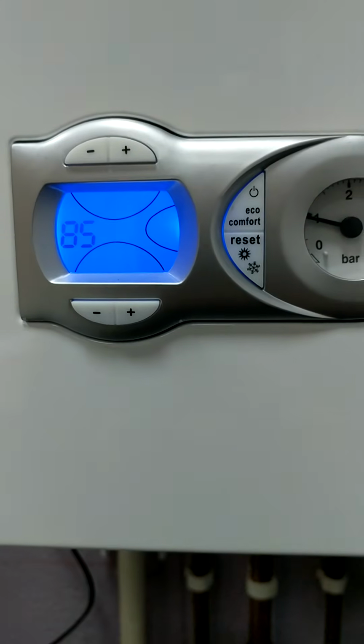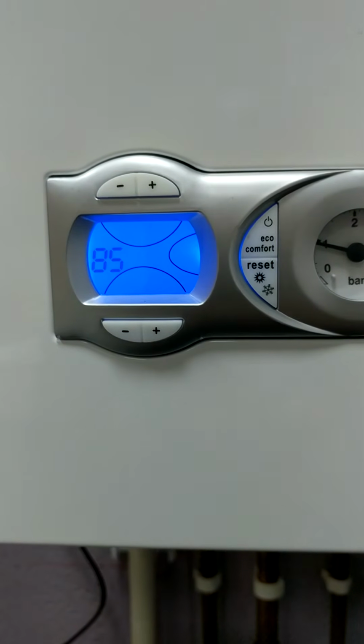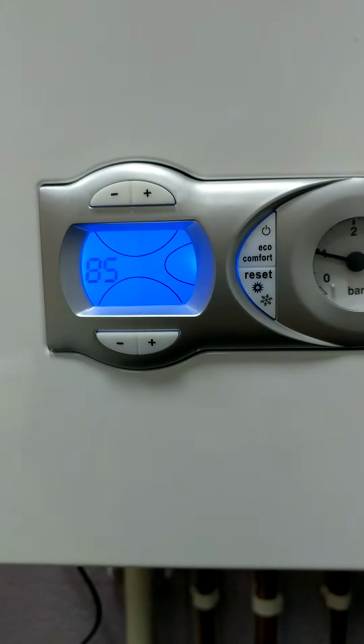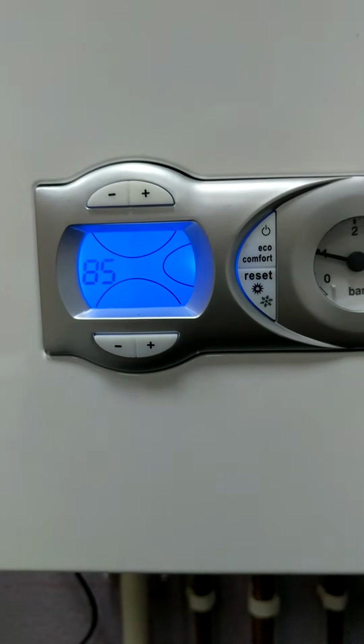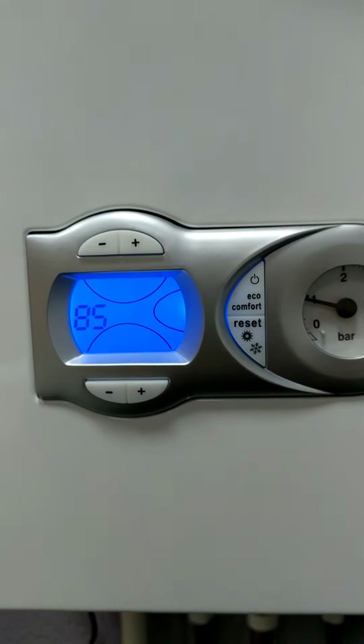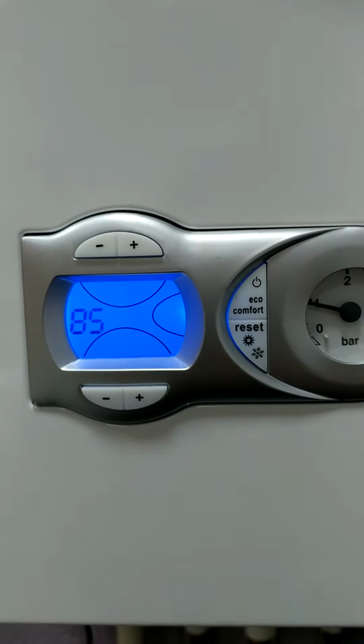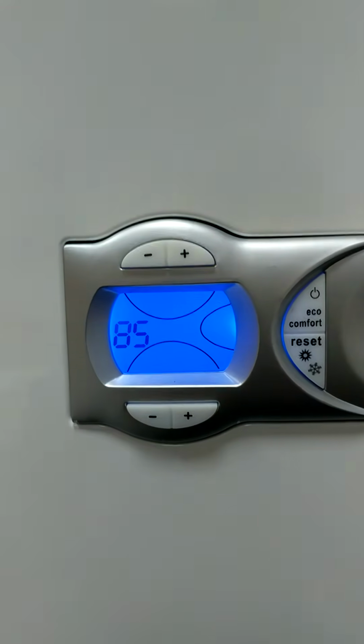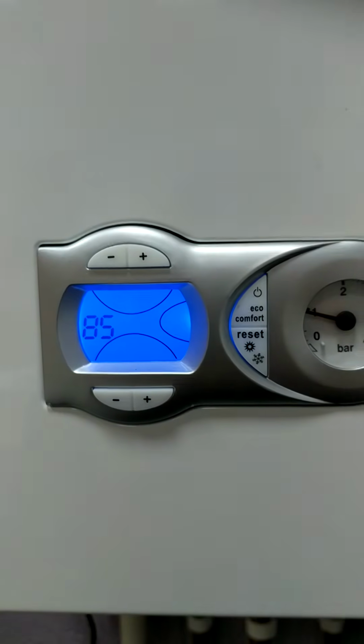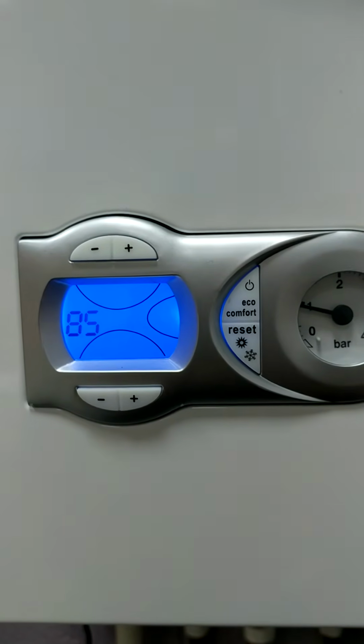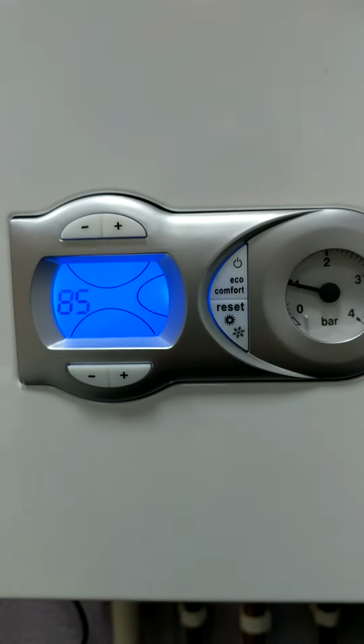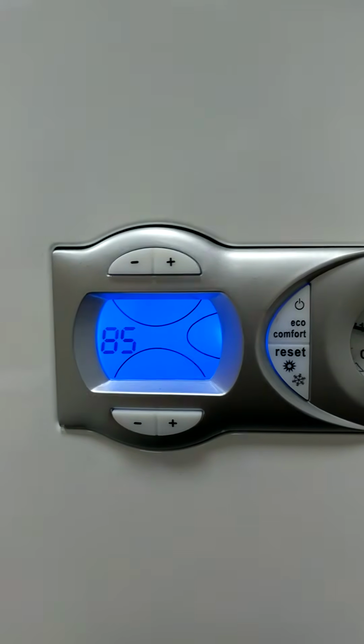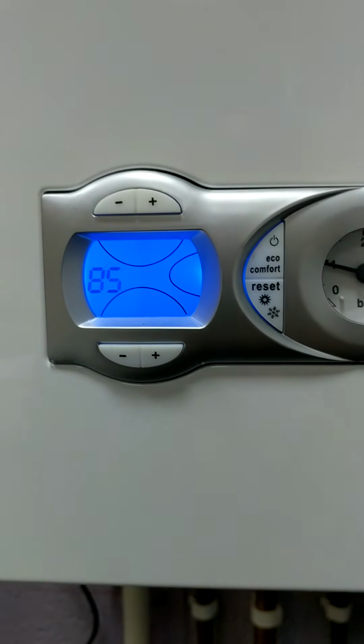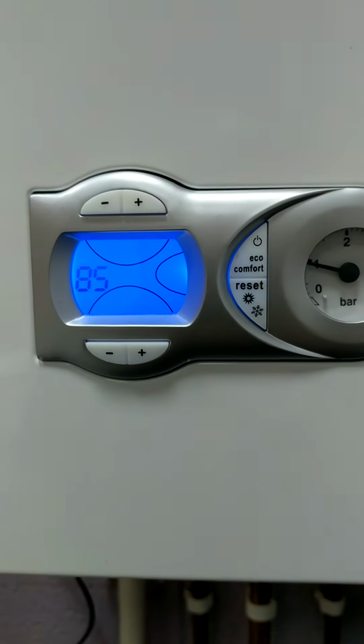What I will say, when you do commission the boiler, make sure you do your commissioning first, so you can get your kilowatts, you range rate it, and you get all the correct kilowattage and range rated temperatures and kilowatts that you use. Then after you've done that and you fill in the benchmark, then you can range rate it down. Because if it's a 25 kilowatt boiler and you set it up and you try and range rate it, you might end up coming into about a 12 kilowatt boiler, and obviously all your paperwork's going to be wrong then.